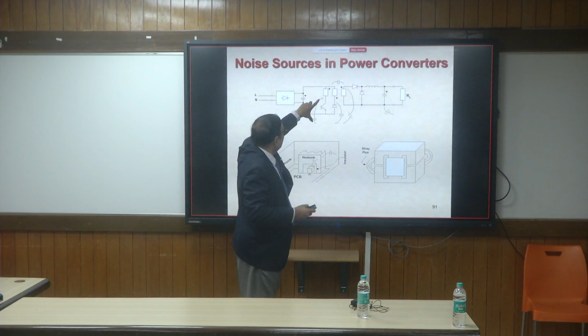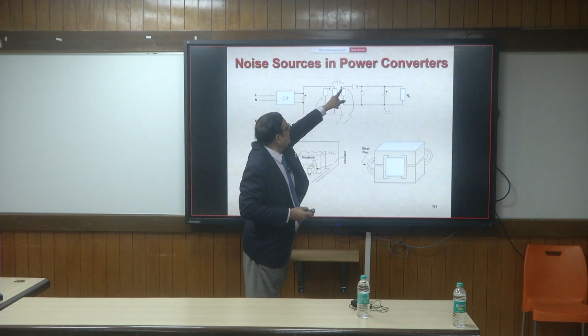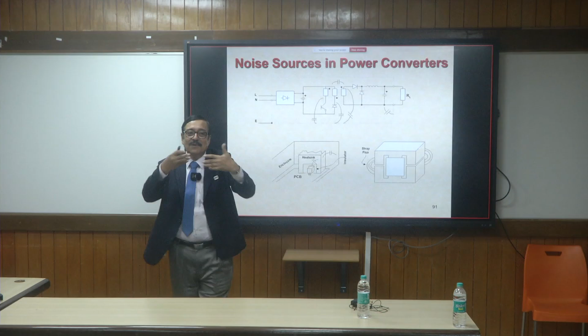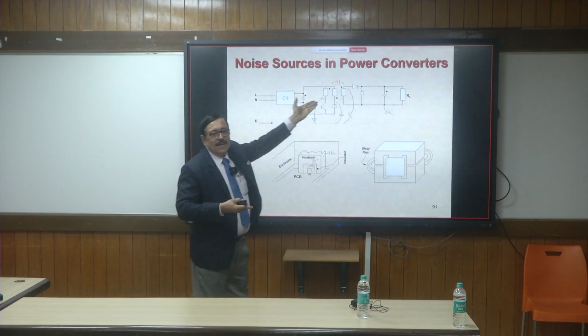There is a dotted line showing the outer box of the equipment, and this potential is changing. It's once going to ground reference and going up. So you have a changing potential. There is a stray capacitive coupling. That's what I said. You can't see it, but it is there. It's a network of capacitance. So potential is changing. This potential can change, this can change. You have capacitance between the windings because the two windings are separated by dielectric, and so on. The catch is, in a network of capacitances, if everything is steady, all the voltages are steady. If you change one voltage, then the network is disturbed and the current will flow through some of the elements trying to restore another stable point. So that is where the noise spreads to the other side of the system, because you are disturbing the network through some mechanisms.